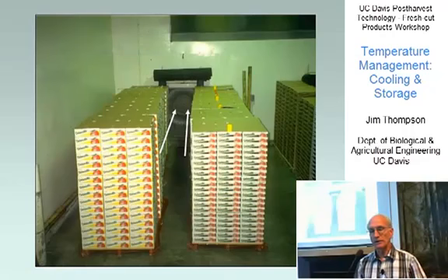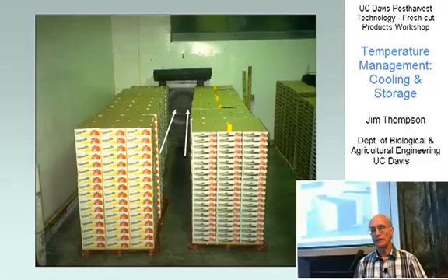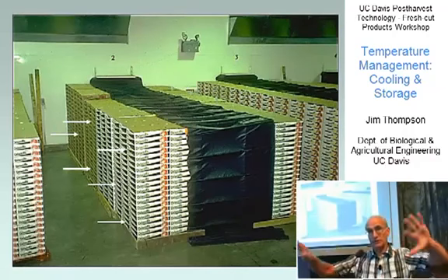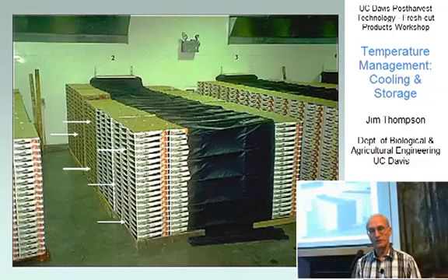Here you can see a picture with strawberries. You'll see the fan in the back. The tarp is black. It hasn't been unfurled yet, but it will be rolled out, cover that open area, and the air will flow through the berries and return to that fan, be recooled, and then the air is recirculated in the room. And this is a picture with the tarp in place. The fan is on. You notice how the black tarp is kind of sucked down because of the negative pressure in that return column.